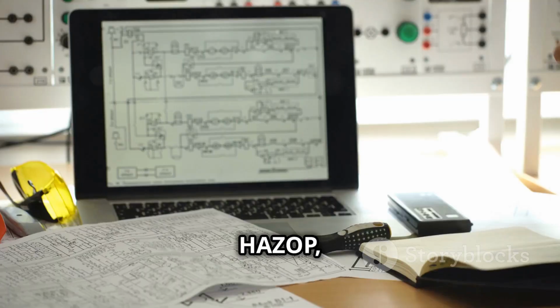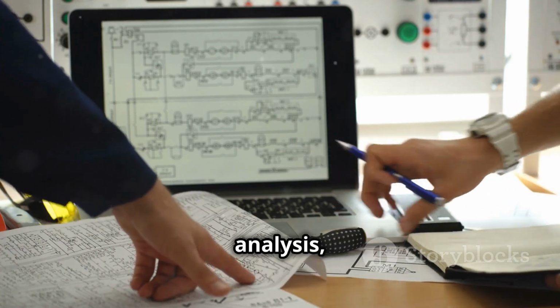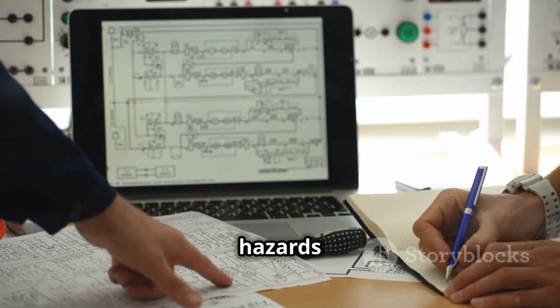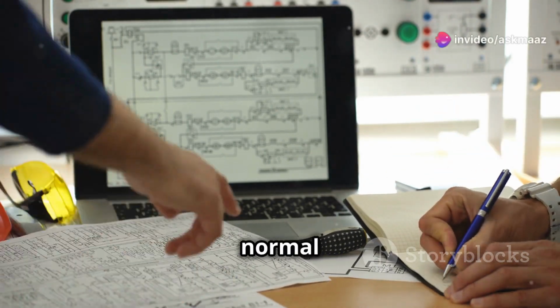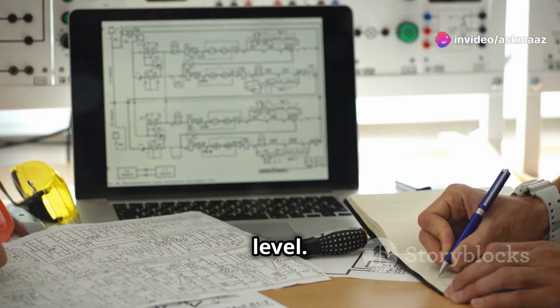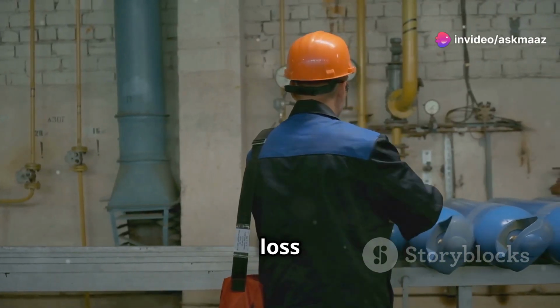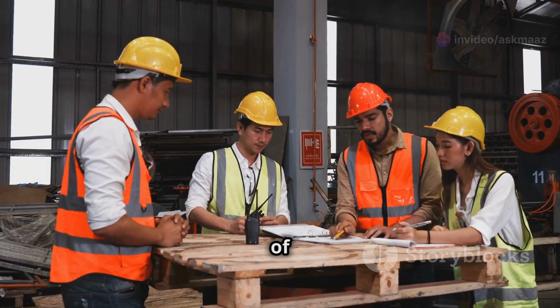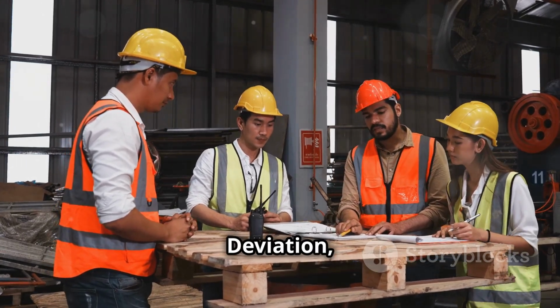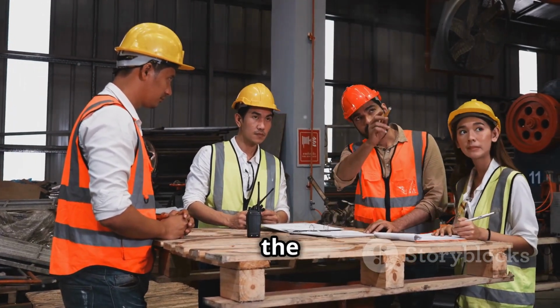HAZOP. HAZOP, or Hazard and Operability Analysis, is a method to identify process hazards by analyzing deviations from normal conditions at the P and ID level. It focuses on equipment function loss and human error. Key elements of HAZOP sessions are deviation, cause of the deviation, consequence of the deviation, and installed safeguards.